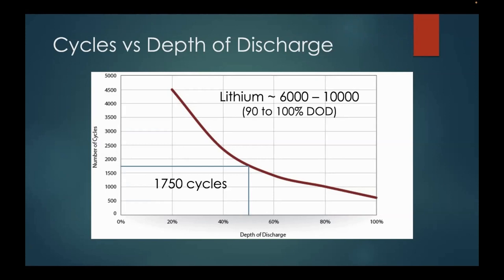When we contrast that with lithium, a typical lithium battery bank gives you 6,000 to 10,000 cycles, and you don't stop at 50%, you can go down to 10% or even lower. So there's a lot of benefit to lithium, and the reason it's taken off in the last 5 years is because the price has come down.